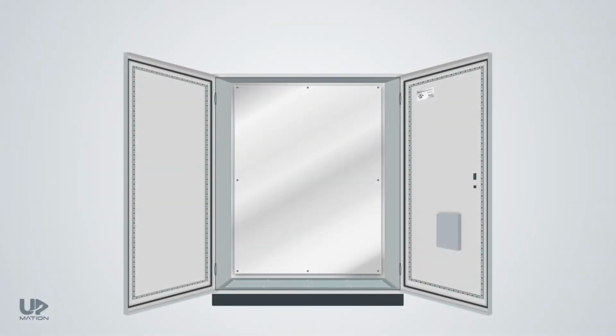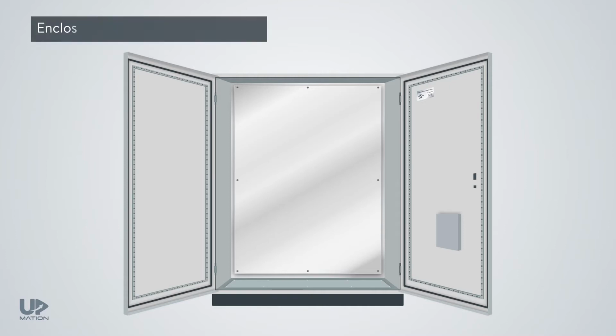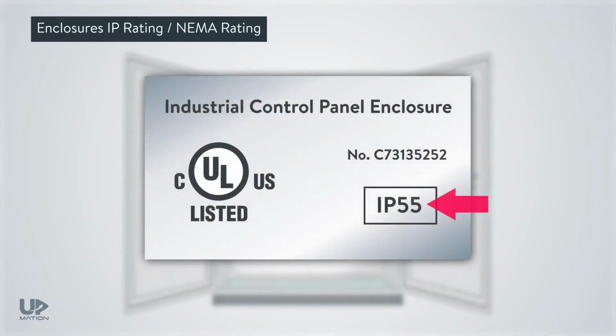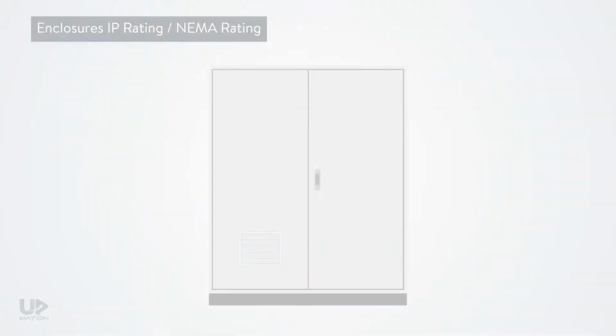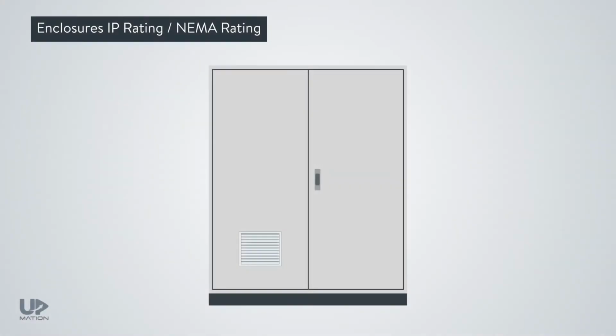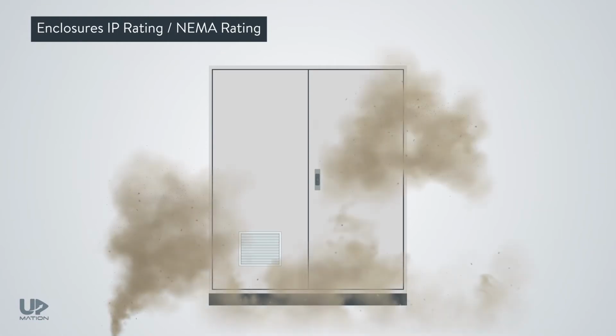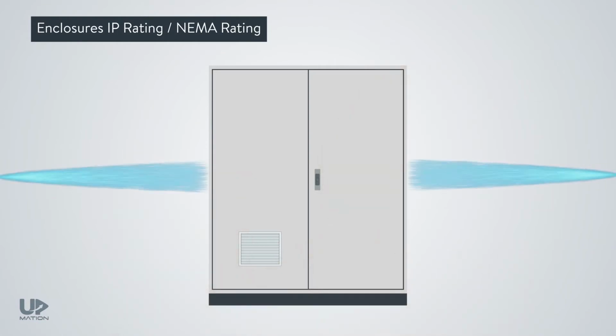An important point about the electrical panel enclosures is their ingress protection rating, or IP rating, and their NEMA rating. The IP rating, which you can usually find on a label within the enclosure, is a two-figure code that shows the level of resistance against dust and liquids. For example, a device with an IP55 level has limited ingress protection against dust, and of course, low-pressure jets of water from all directions.